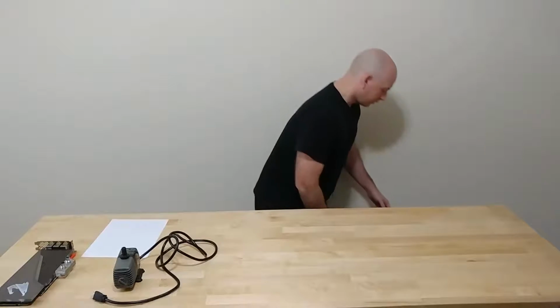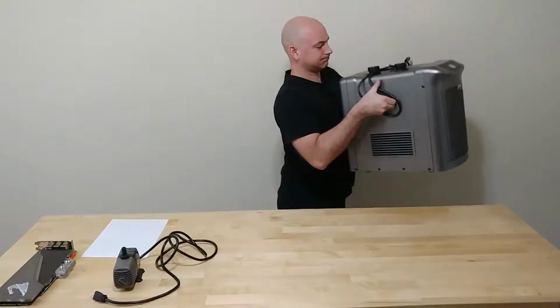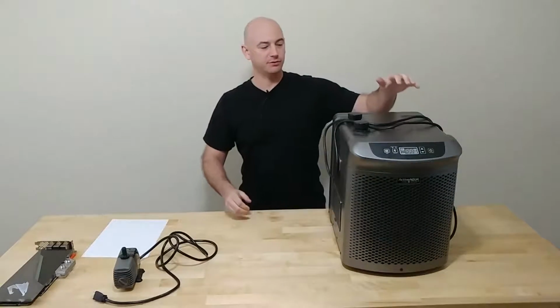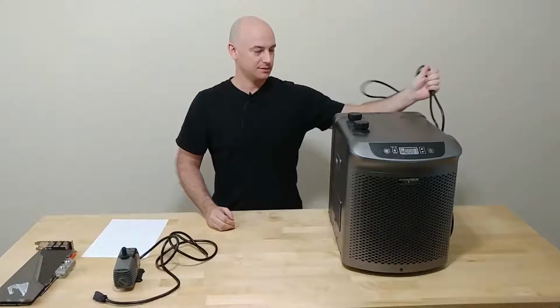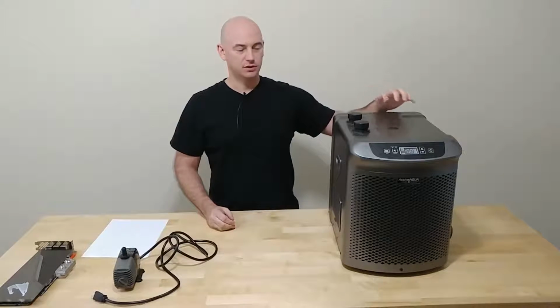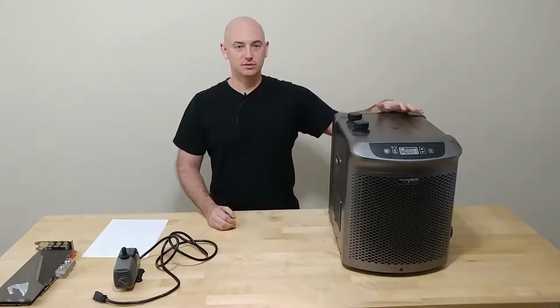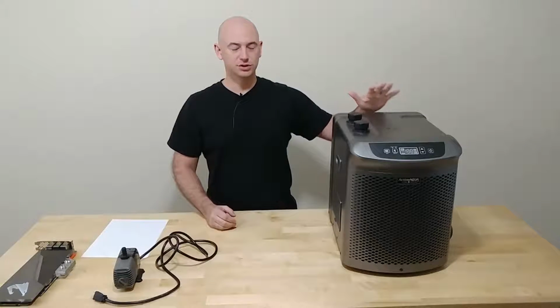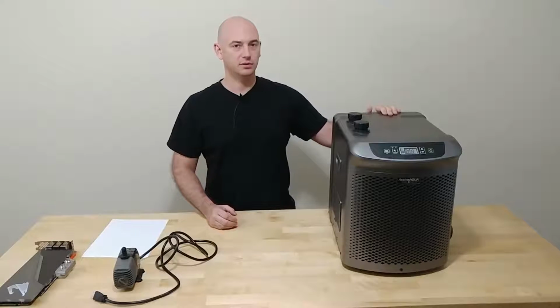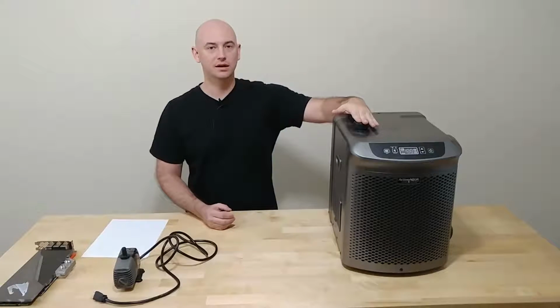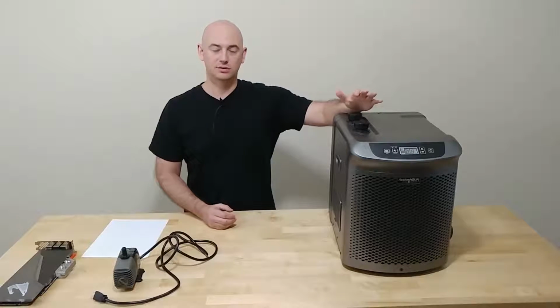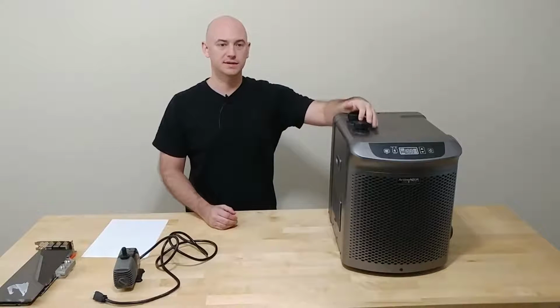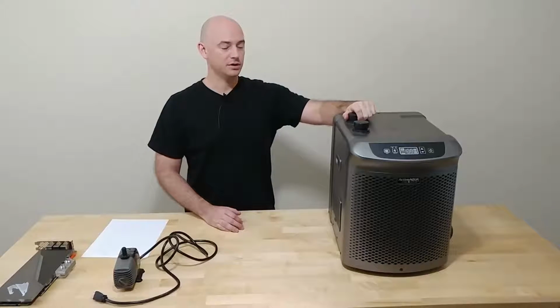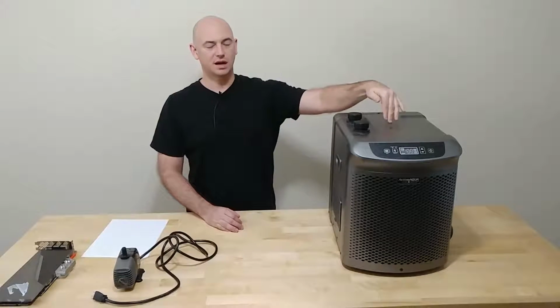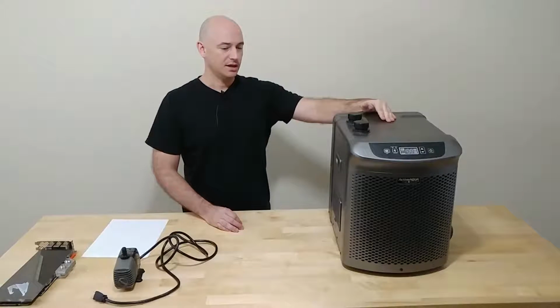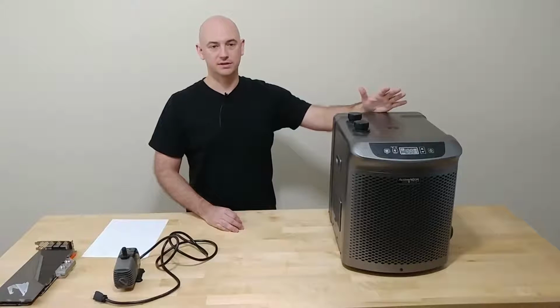So how are we going to chill the water? Well, you may have seen one of these before. Again, this is an aquarium chiller, similar to the kind of chiller that a certain company used to chill their CPUs at an event recently. But this one just chills water using a refrigerant. It uses R134a to chill the water in an internal tank down to a temperature, and it can go down to about 1 or 2 degrees. Below that it'll freeze the water, and you don't want it to get any colder than that. So it's got a stop in here. It won't let it get colder than that. And for our purposes, we went down to about 7 degrees water temperature.